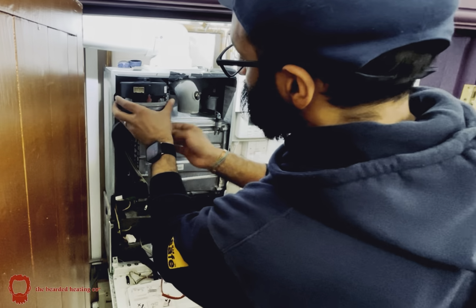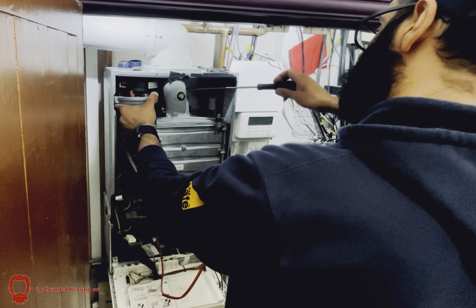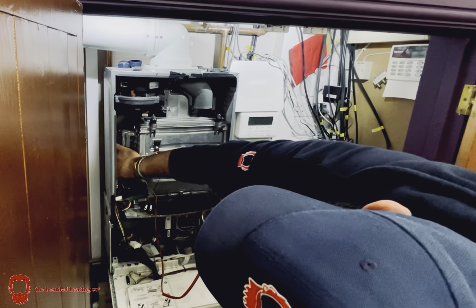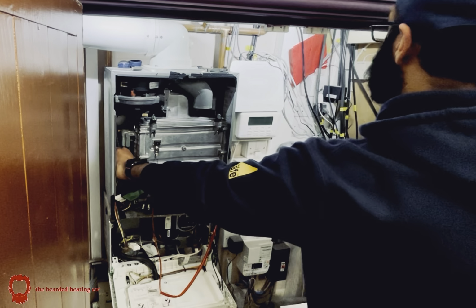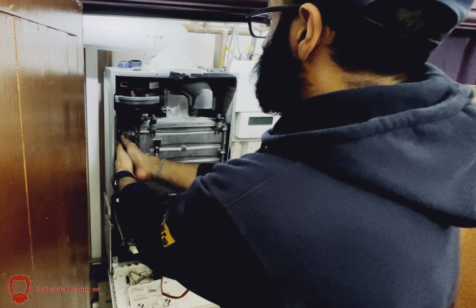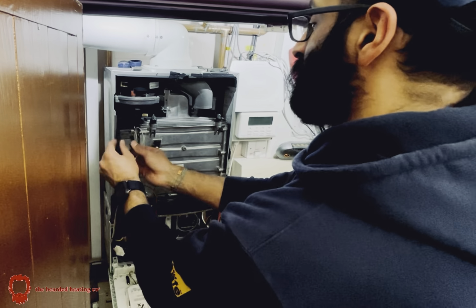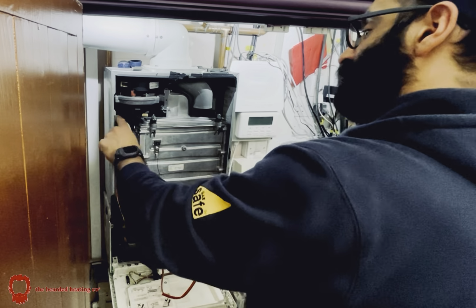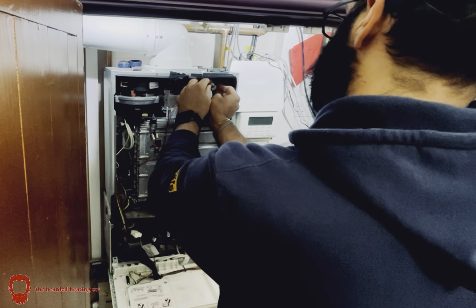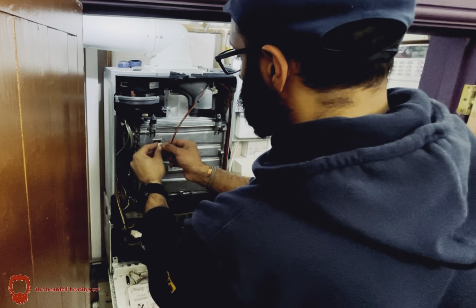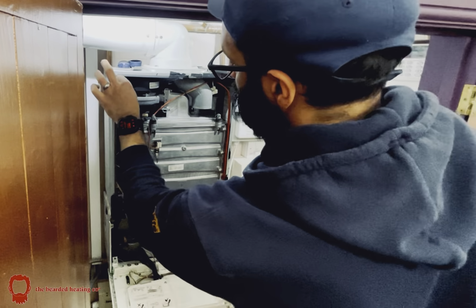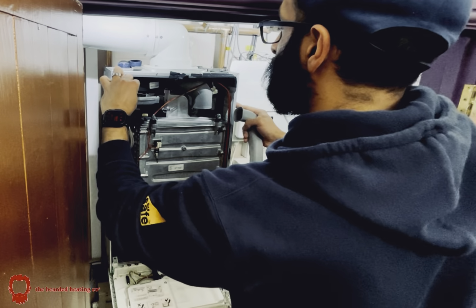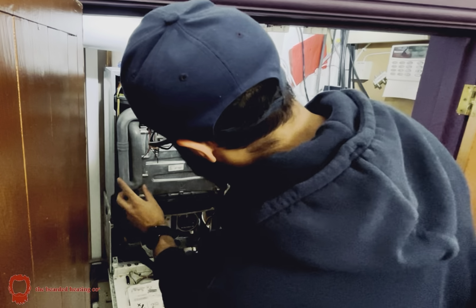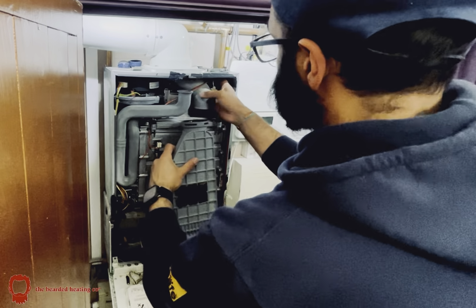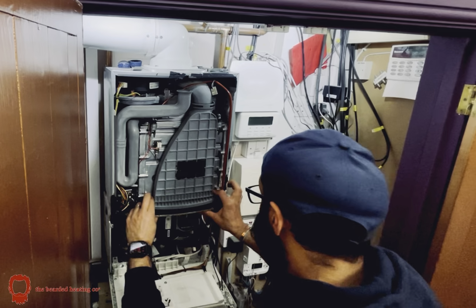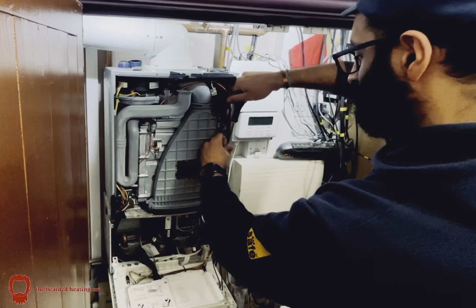Fan goes back in. Two screws hold the fan. Gas connection done. There's a little washer in there, make sure you don't forget to put that back in. And there you go, it's hand tightened. Ignition transformer clip back in place. Connect all the electrics back up. Fan connection back on. Don't forget the earth of the fan. And that's the air intake pipe put back in. And the flue collector pushed back in, and then the two screws to just hold it in place.